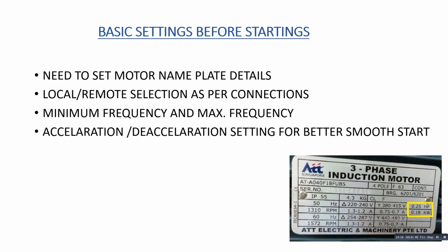Then you have to make sure of the control mode, whether you will control in local mode or remote mode. So you have to set these things accordingly in the VFDs. Then you have to set your frequency, minimum frequency and maximum frequency.